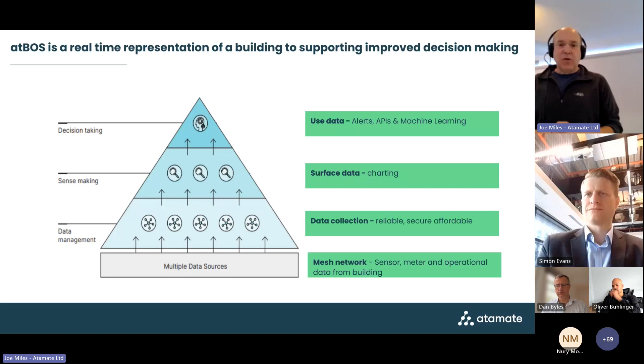First of all, looking at some occupancy-based heating - I've just grabbed these screen grabs. On the left-hand side we've got essentially a thermostat working, controlling the temperature in this room. Here's an electric heater being turned on and off, hence the pink color, to hold that temperature constant. Then we've got the occupancy - all of the occupancy in our system is a combination of passive infrared, like a burglar alarm type sensor, and carbon dioxide. Those two sensors together is how we produce an occupancy level.